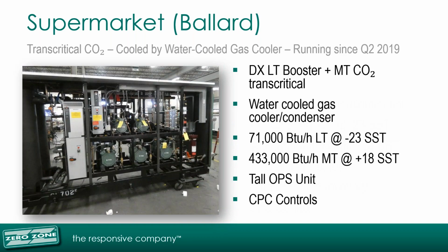Here's another transcritical booster system. This unit has a sheet metal enclosure to house the refrigeration system. This particular unit was installed in the parking garage under the store. The biggest challenge we had was maintaining proper superheat at the rack. With all the suction lines running downhill to the rack and all running through cool spaces, superheat control at the cases was crucial. Our field service team assisted the contractor to provide a reliable, long-term solution.